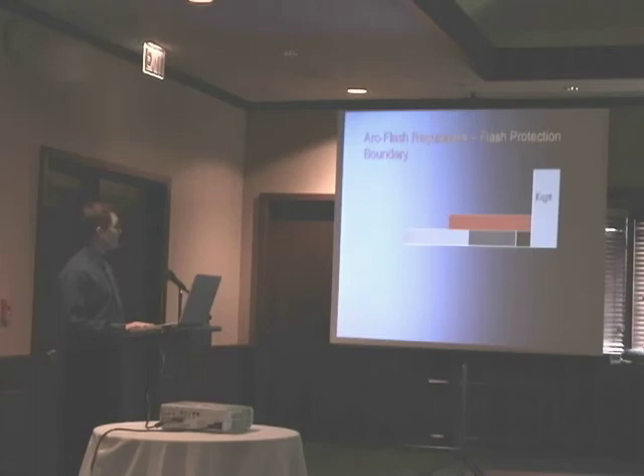Okay, lastly, we have the flash protection boundary. This is the closest approach by qualified or unqualified persons without PPE. This distance is set at 4 feet for systems between 50 and 600 volts. It may be reduced to a distance where a worker could be exposed to 1.2 calories per centimeter squared for 0.1 seconds. Now, the reason it says that is if you have a correct arc flash study, there will be more specific flash protection boundaries labeled in our binders, or in binders and on the equipment.